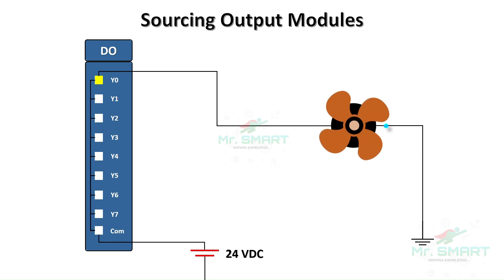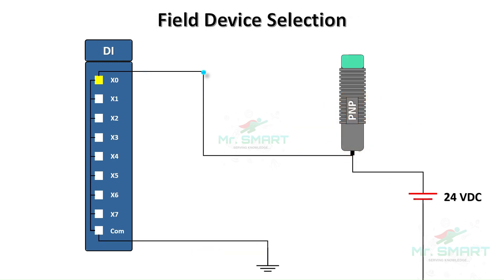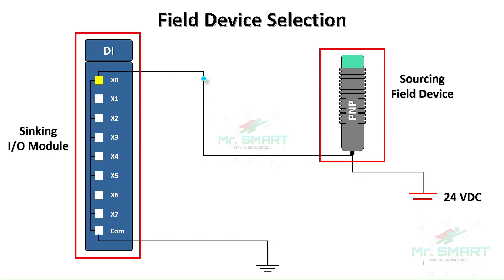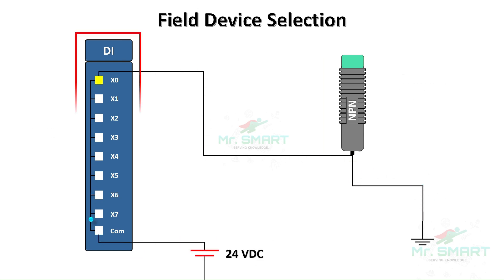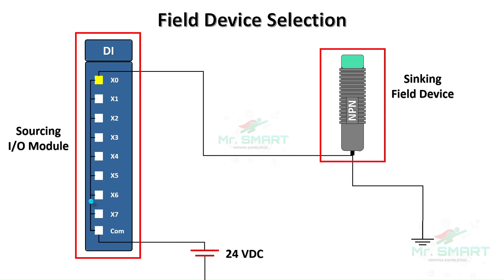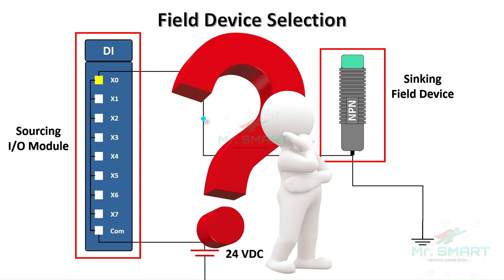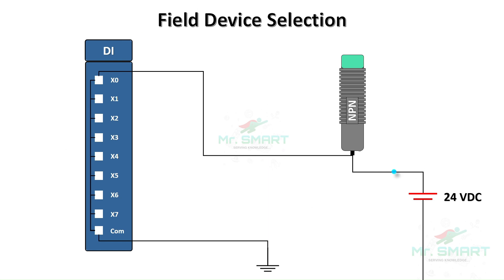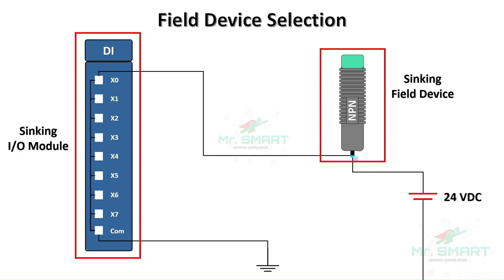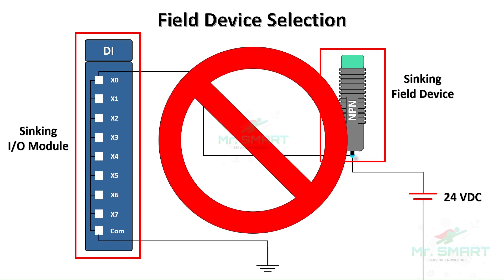Practically, most output devices can work with signals from both sinking and sourcing modules. But it's important to remember this rule while selecting your input devices such as sensors: a sourcing-type field device must be connected to a sinking I/O module, and a sinking-type field device must be connected to a sourcing I/O module. This is all about completing the circuit correctly.